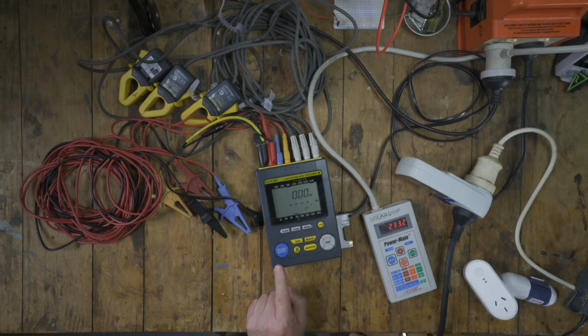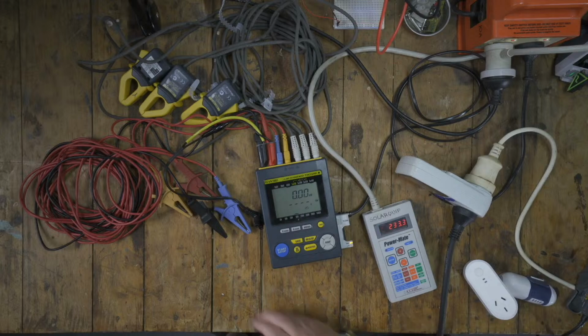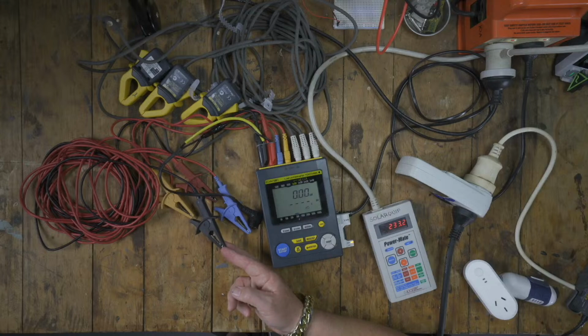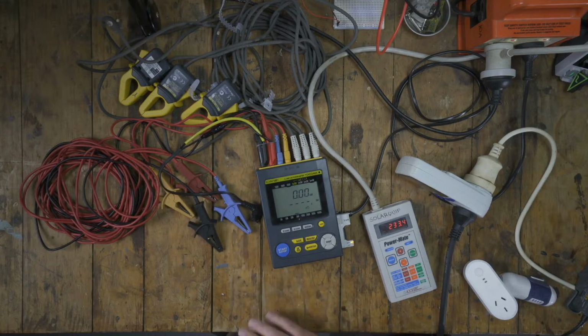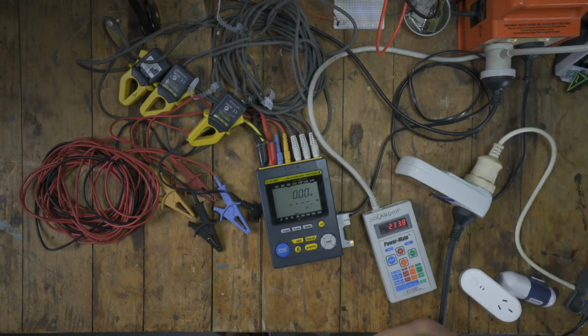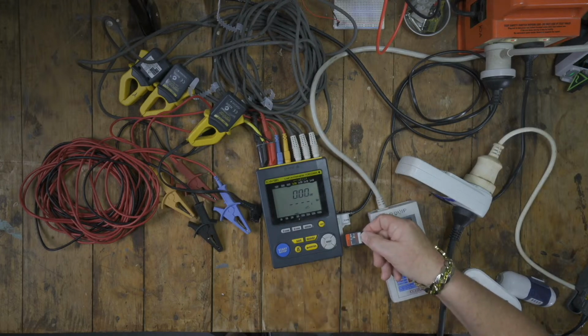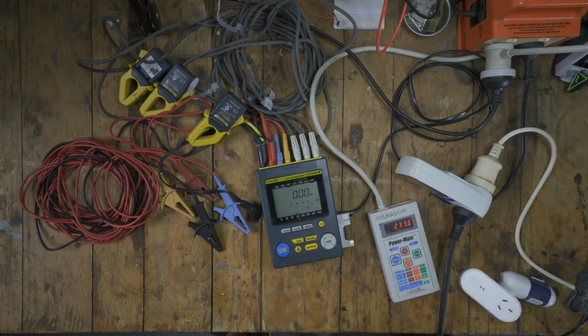This is a power quality meter, and it has to be installed by an electrician because it gets connected directly in the switchboard. They open up the switchboard - these are the voltage connectors, and these are the current connectors, so it can measure current. It logs data, and you can set the logging interval down to 1 second. I've used this to get very detailed analysis - it logs to an SD card in CSV format, and you can pop it into Excel and do graphs showing how terrible the voltage characteristics are in your home or business. It also measures power and energy.